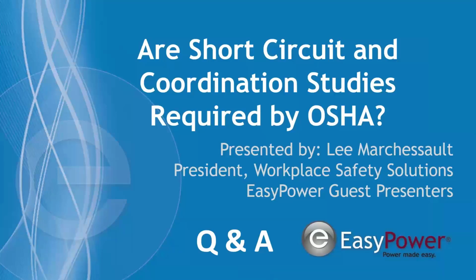If I go into a fuse disconnect switch, the fuse doesn't help me there. If you had a load side fault, they will help. They'll trip quickly. But on the line side of the fuse, it doesn't do anything for you. So it's still the same hazardous level as whatever's upstream, as far as opening that disconnect. If upstream is very, very low, then it's probably still going to be low unless it's a long way away.